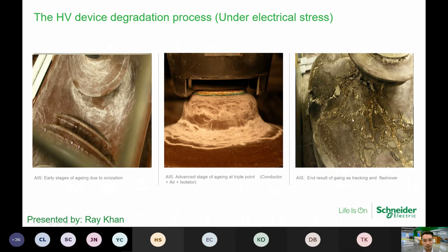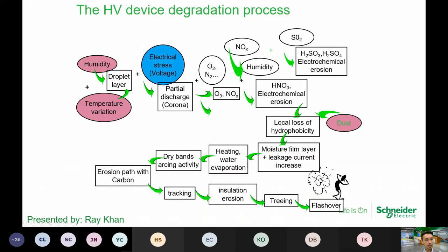So you can see here we have this tracking stain that has actually occurred. All of this takes place from the erosion of the insulation itself. These are pretty dangerous because these are already the formation of the flashover, which starts to take place. All right, so the flashover can cause a lot of issues like internal arc fault, which can result in fire and explosion. And it can also cause other issues like short circuit and arc fault. All right, so this slide pretty much is the progression slide.